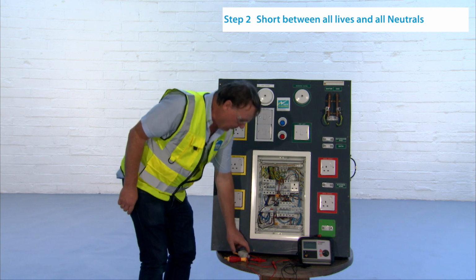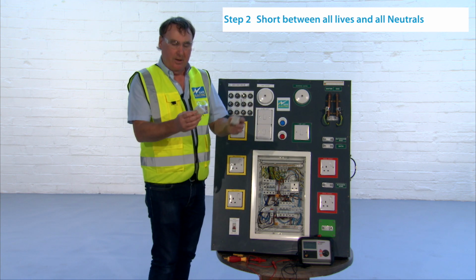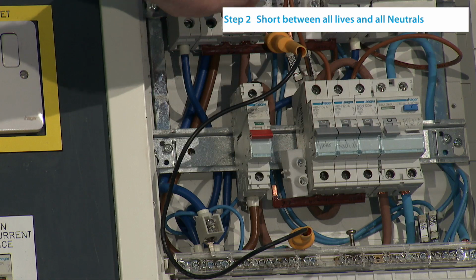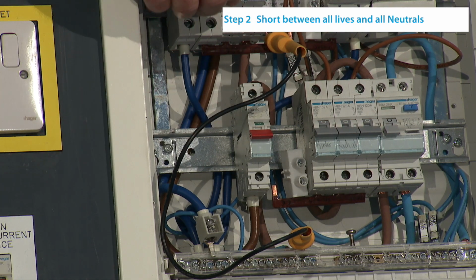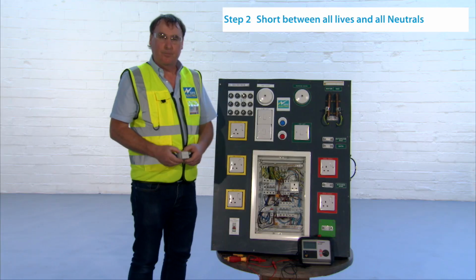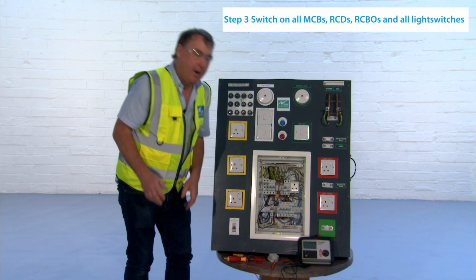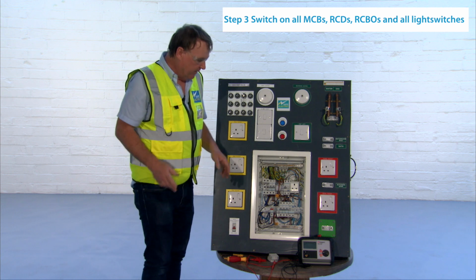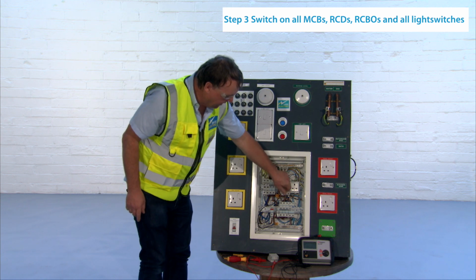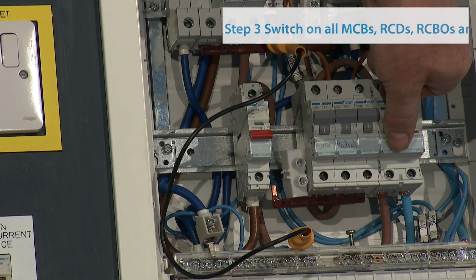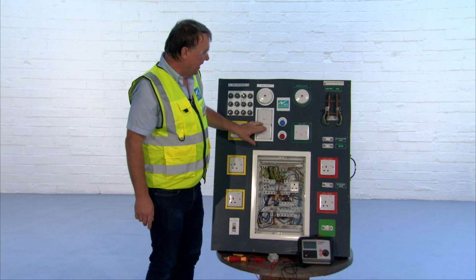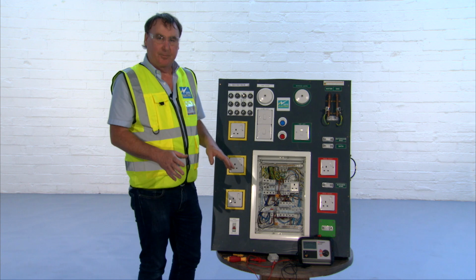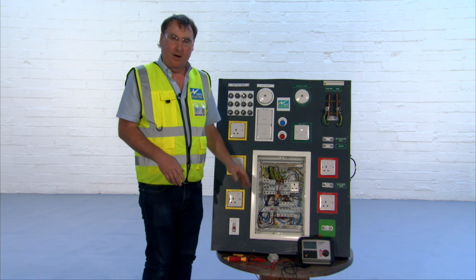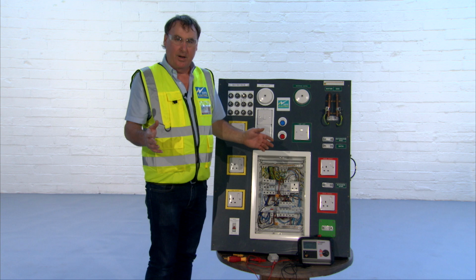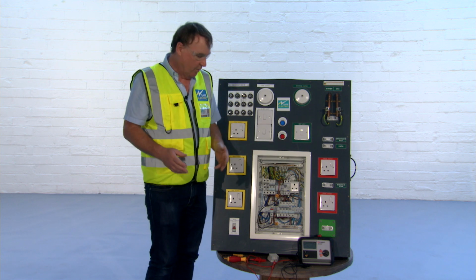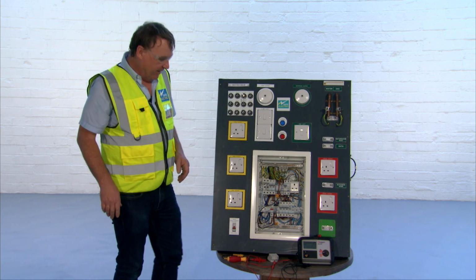Step number three, in this particular installation, we have surge protection. The surge protectors were plug-out devices. They were sitting there, so we remove the surge protection. And the very last step might seem obvious, but it's really important. Switch on all your MCBs, RCDs, RCBOs, and your light switches. Everything has to be switched on. If we turn off all the circuit breakers, we'll get a brilliant reading, but we haven't tested anything. Okay? Now we're ready to carry out the test.